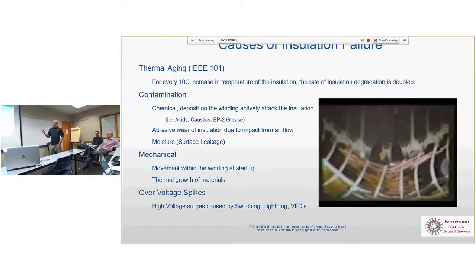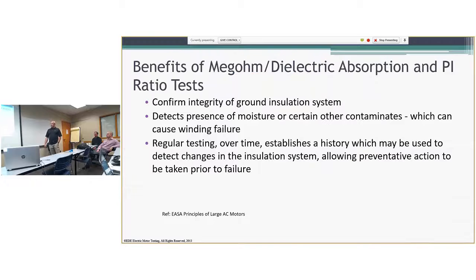Detecting the presence of moisture, that's a huge one. Also, like you were asking, if the motor sits for a while, that's one of the problems with it being cold, or if it's in any kind of humid or outside location, it tends to draw moisture, and that will definitely bring your Megger readings down. And it's all stuff that you want to know before you hit the start button, or a lot of people want to know it's going to blow up when you hit it.